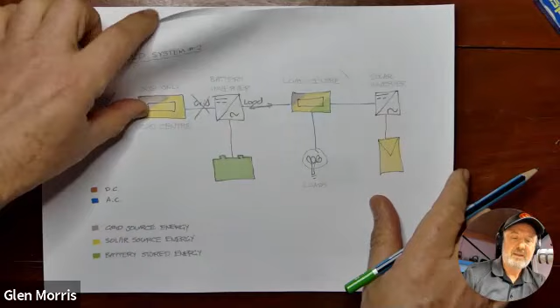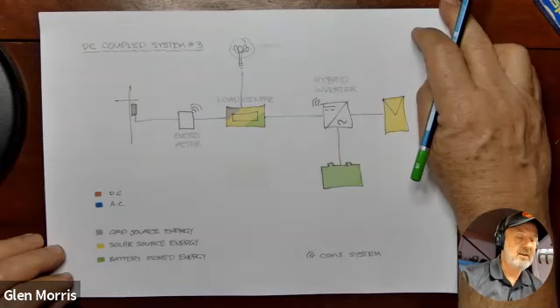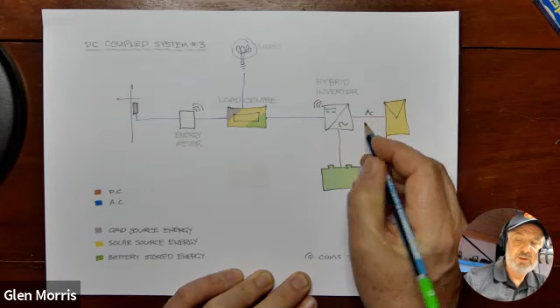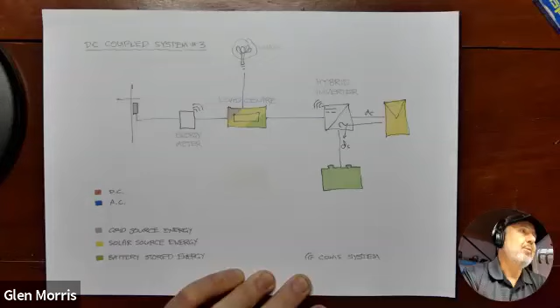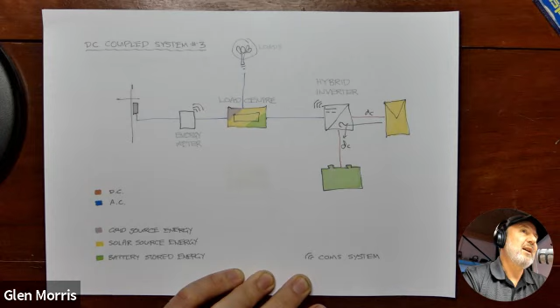So here we've got a DC coupled system. Now remember I said coupling is how does the solar energy get to the battery, and in this case it's going from the solar panel, which is DC, orange line, to the battery, DC. So it's going internally through that unit. It's not getting converted to AC to charge the battery. So the advantage with a DC coupled system is it doesn't actually need the grid to charge the battery. So you'll still be able to charge the battery without the grid.